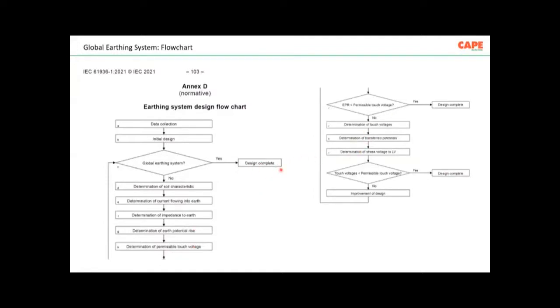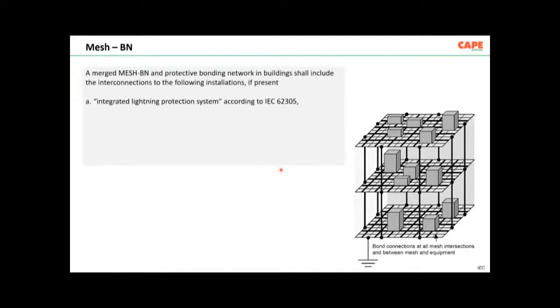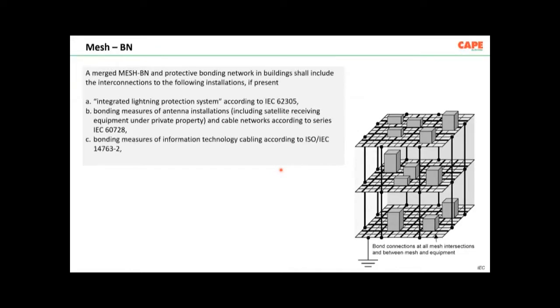You just go for a global earthing system, but ensure that the shock voltages are reduced to less than the limit which I have shown in one of the slides. Modern buildings also require, in addition to the global earthing system, a mesh bonding network. Mesh bonding network means the structural steel elements are interconnected in such a way that between the equipment which is installed, the resistances are very much reduced. As a result, you achieve a very high degree of safety, a very high degree of reliability in your electronic equipment.